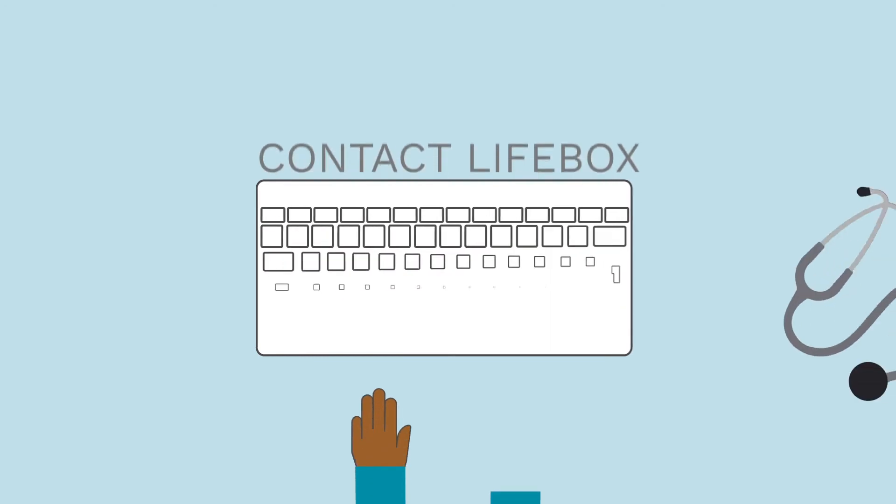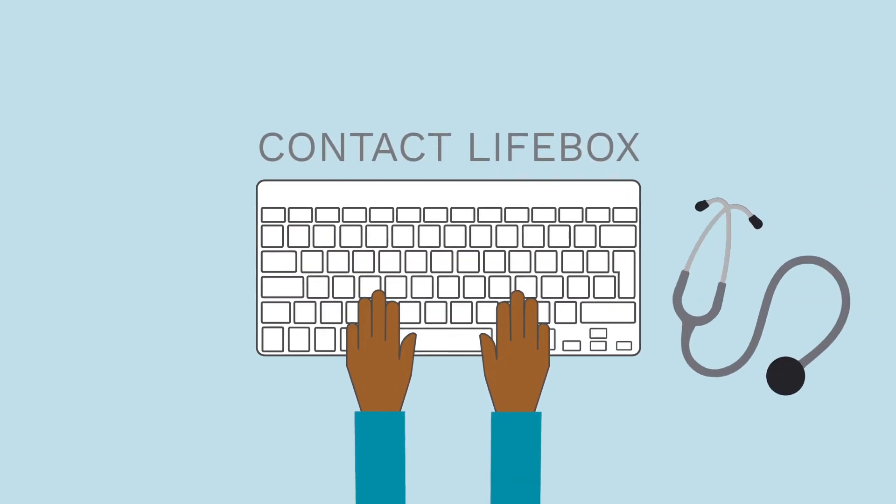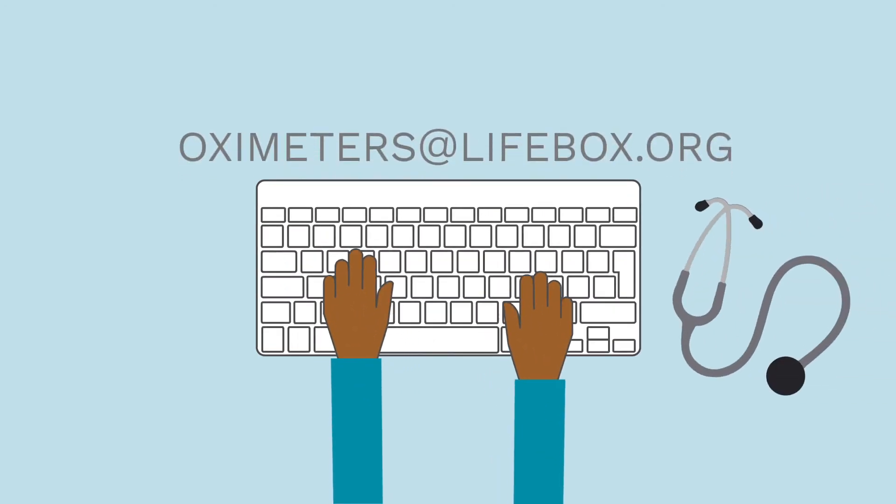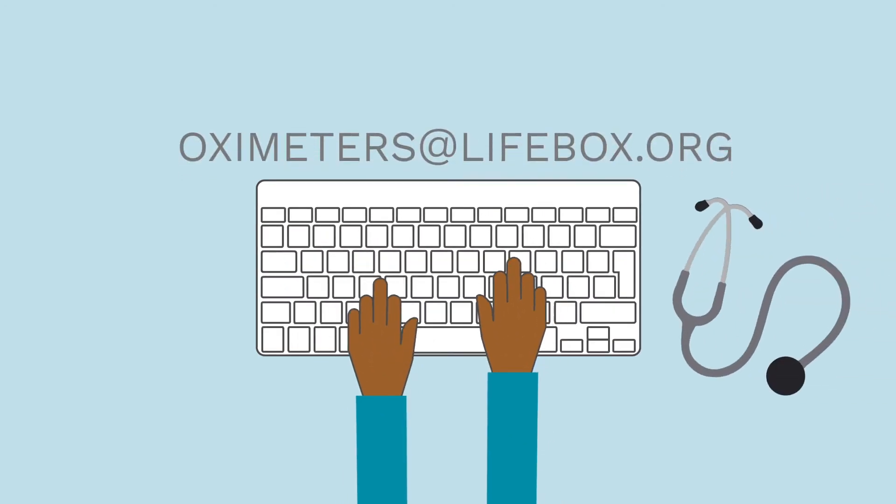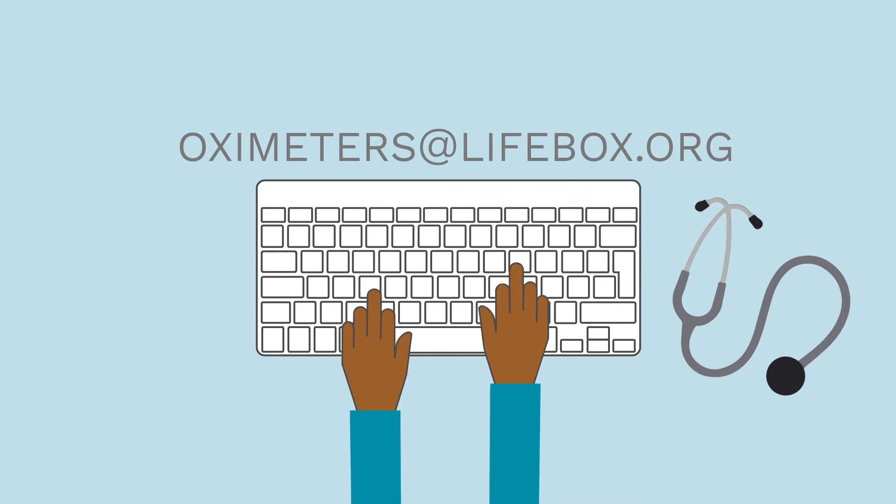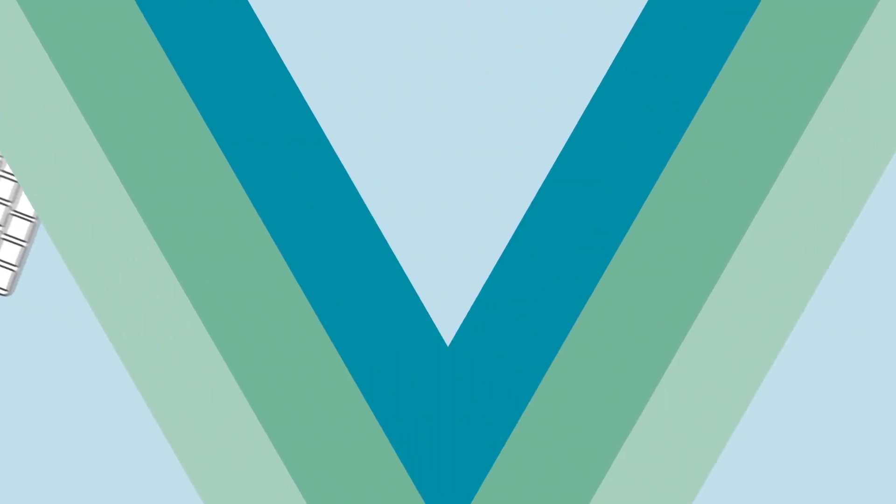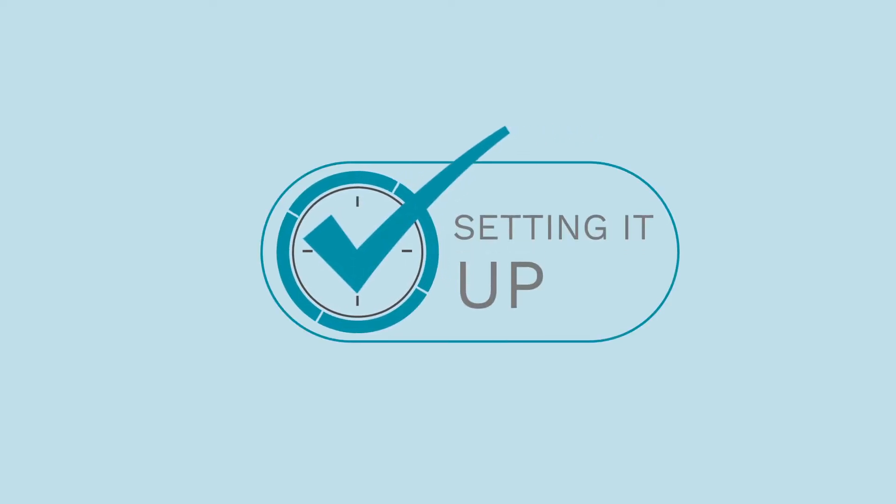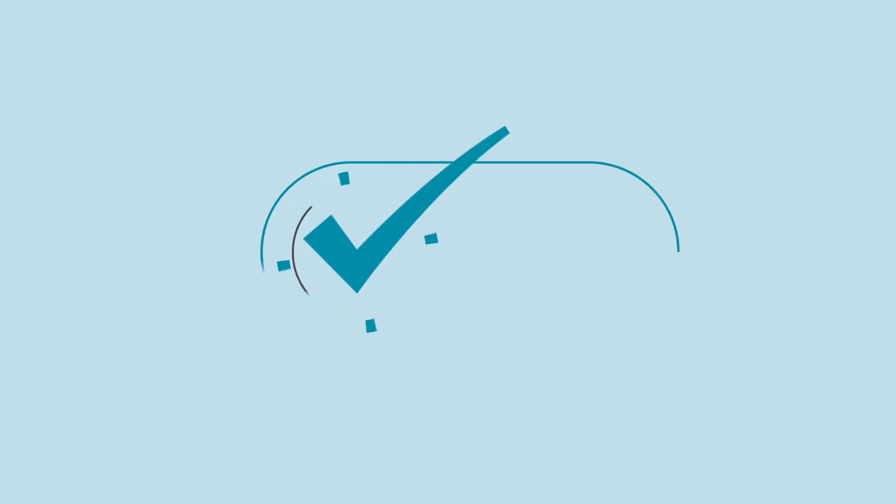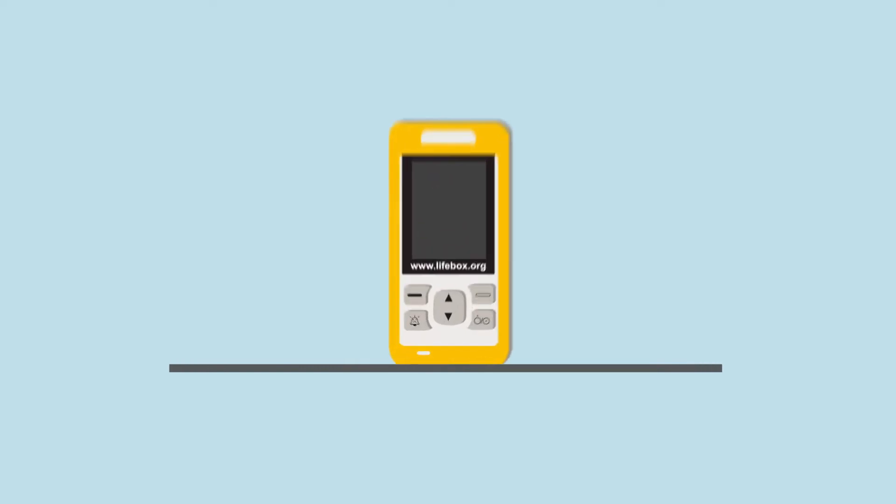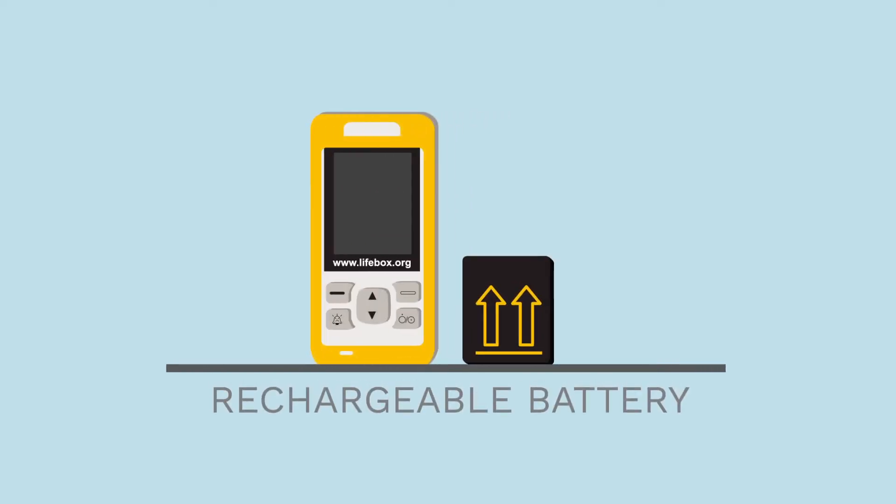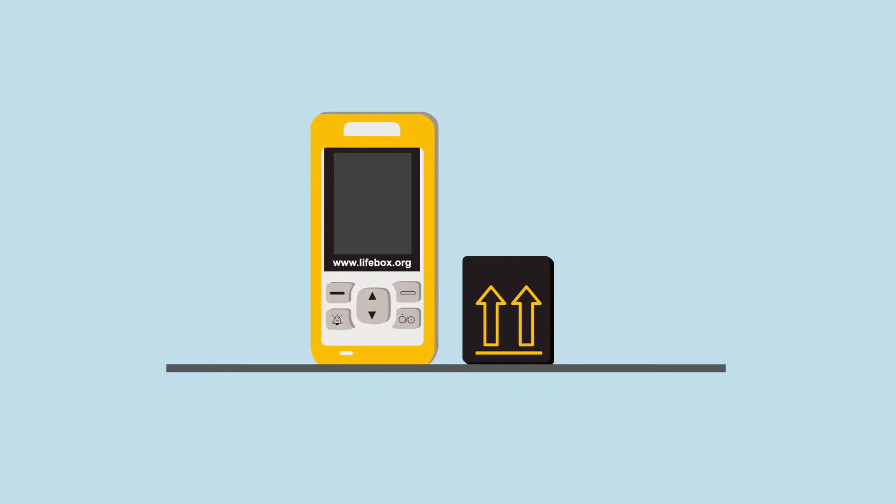If any pieces of the equipment are missing or broken, contact Lifebox immediately by emailing oximeters at lifebox.org. Now that we know what's included in a Lifebox, let's take a look at the steps involved in setting it up. The Lifebox Oximeter is run off a rechargeable battery that's specially designed to fit the Lifebox Oximeter so it won't work with any other device.